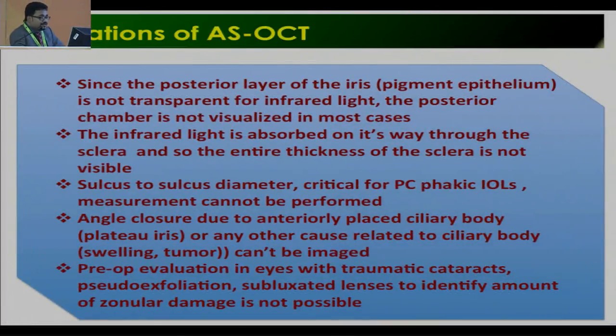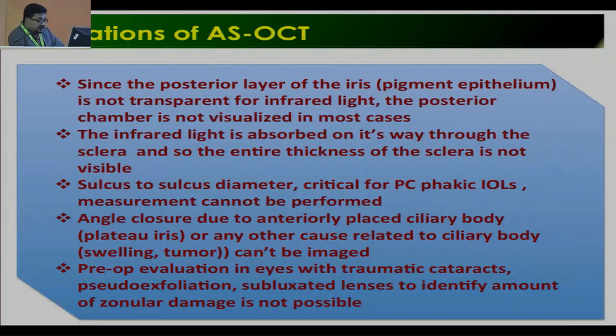The limitations of AS-OCT are: since the posterior layer of the iris pigment epithelium is not transparent to infrared light, the posterior chamber is not visualized in most cases. The infrared light is absorbed through the sclera, so the entire thickness of the sclera is not visible. Sulcus-to-sulcus diameter, critical for phakic IOL measurement, cannot be performed by AS-OCT. Angle closure due to anteriorly placed ciliary body, plateau iris, or causes related to ciliary body swelling cannot be imaged. Evaluation in eyes with traumatic cataract, pseudoexfoliation, or subluxed lenses to identify the amount of zonular dialysis is also not possible by AS-OCT.